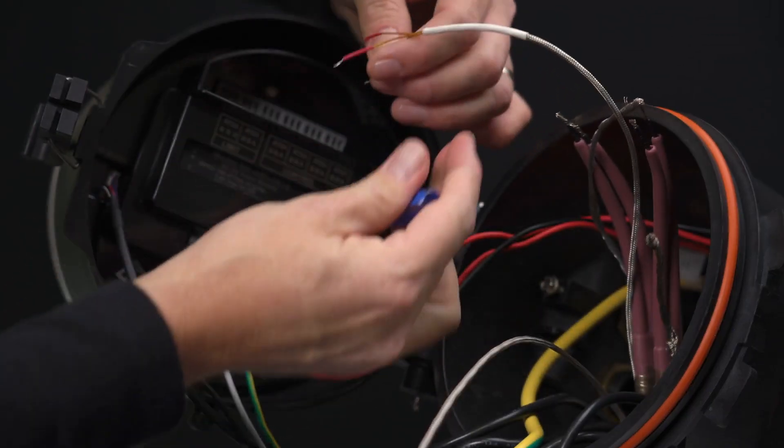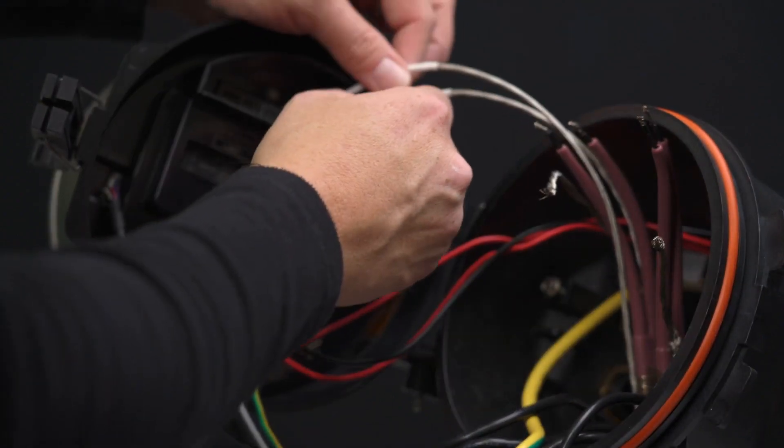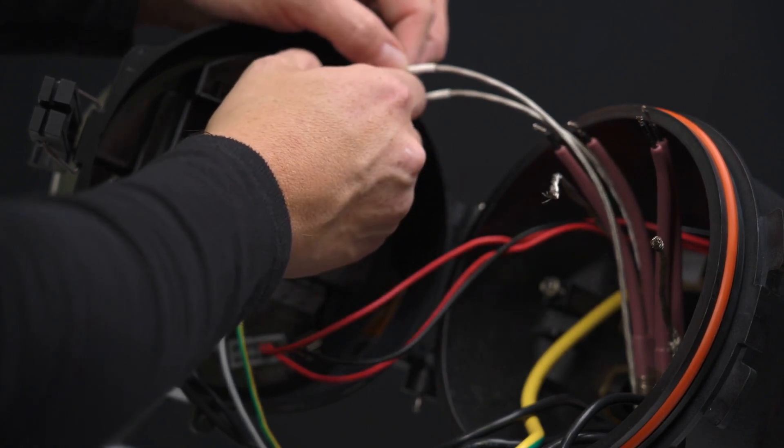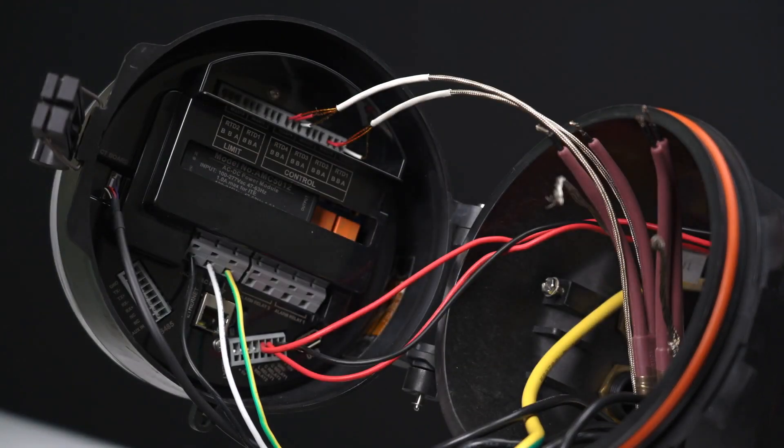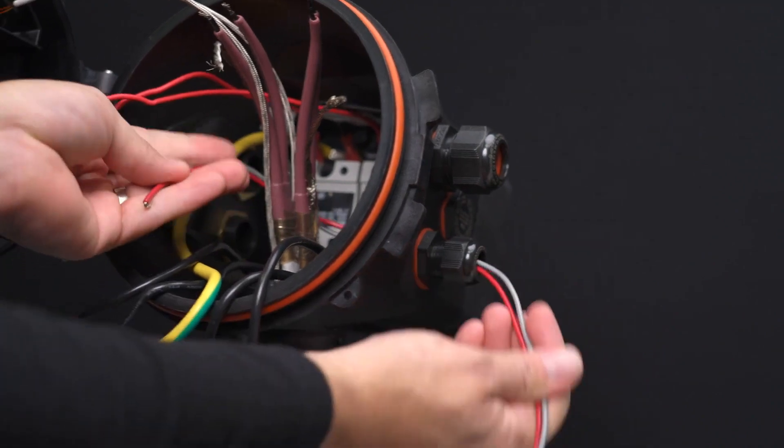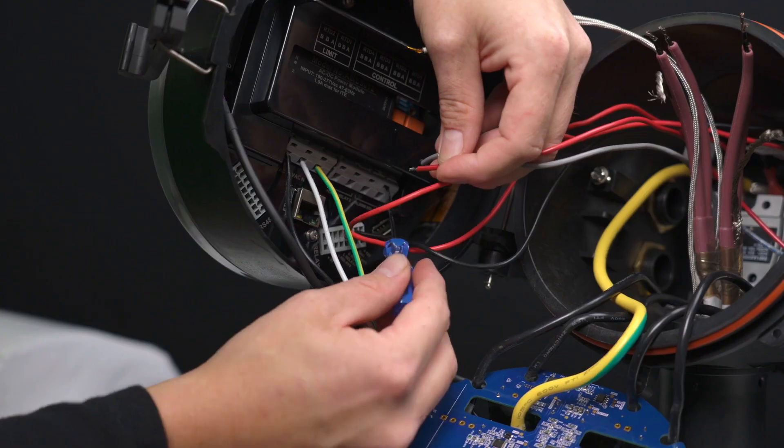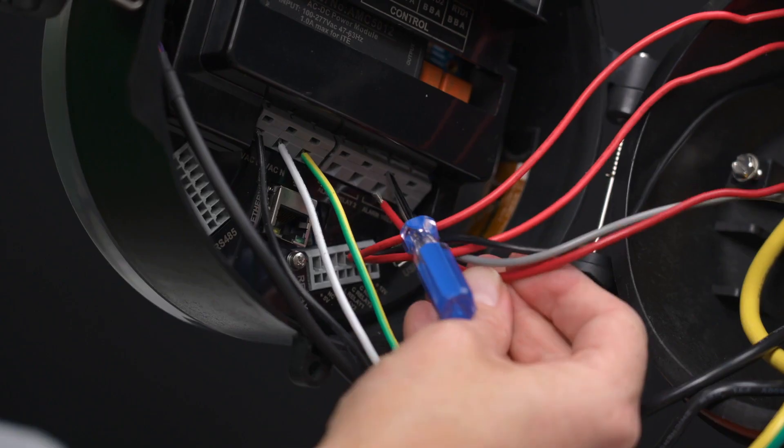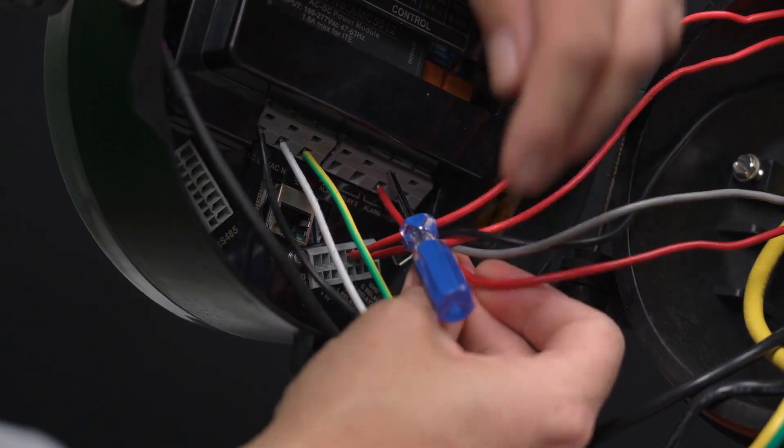Next, land the RTD wires in the front clip. For this, we will use the 2.5mm flathead screwdriver. Route the alarm wires through the cable gland. Land the alarm output wires to the front clip using the same flathead screwdriver.